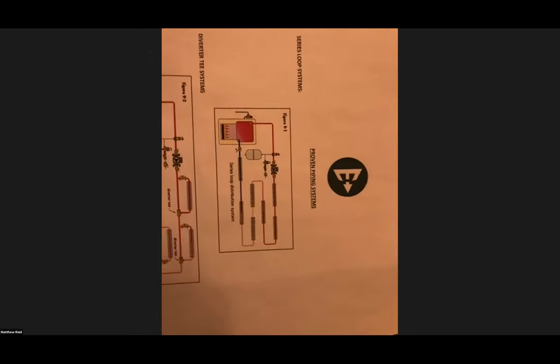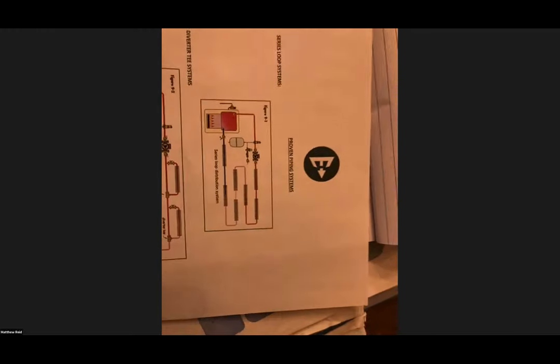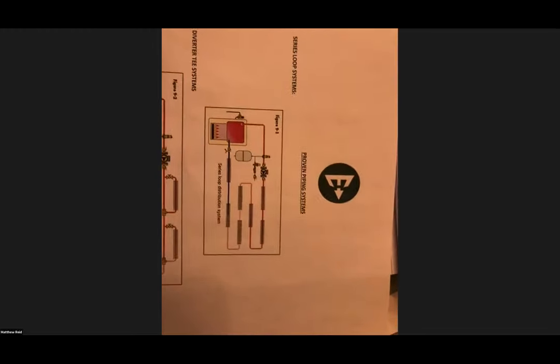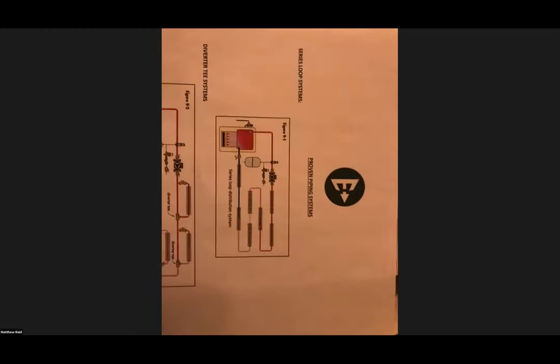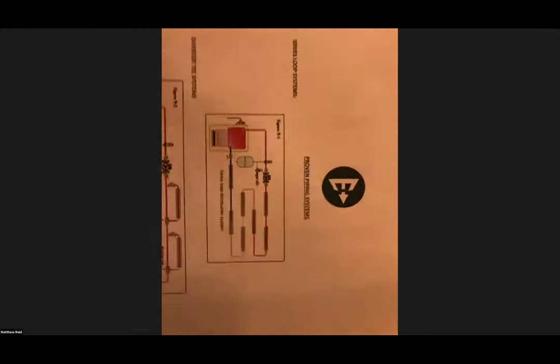Super common question: how do we know what pressure to fill the system to? You take the highest point of the system. You measure the height between the boiler and the highest point of the system. So let's just say that it is 20 feet, a two-story building. You take that height, 20 feet, times it by 0.4, and then add 5. That gives you a fill pressure.